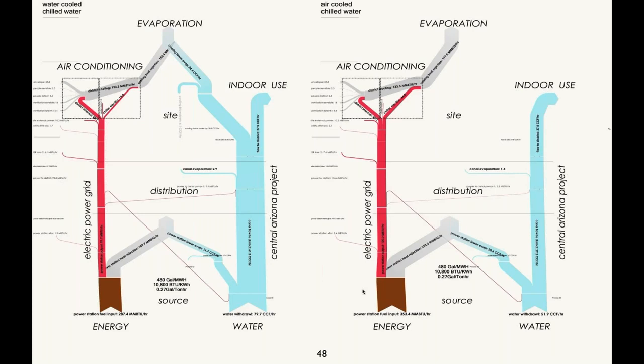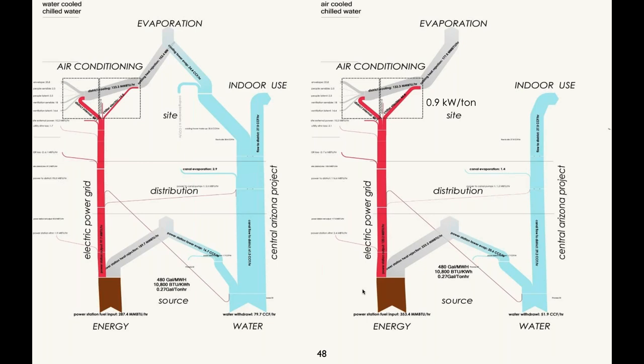In a university setting, maybe that's still always going to be the case. But what you see here is if you had 0.5 kW per ton on a water-cooled system versus 0.9 on an air-cooled system, yeah, we're using a lot more electricity on the air-cooled system. But the effect back at the power plant isn't as significant as you might think. So we're using more water in the case of an air-cooled chiller back at the plant, but it's not enough to compensate for the extra water we're using in a water-cooled system.